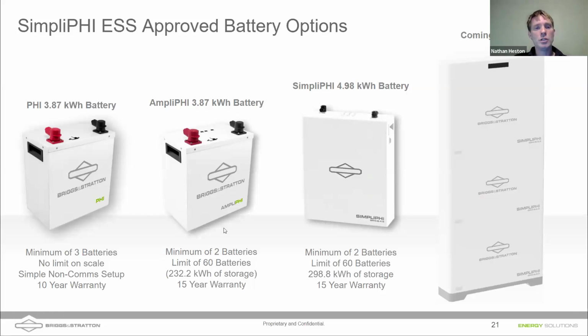There is a limitation for the AmpliPhi batteries, the number of batteries that we can use. It's a limit of 60 batteries. That has to do with the strength of the communication signals and the ability to process as the cabling gets longer and longer in the communications loop.